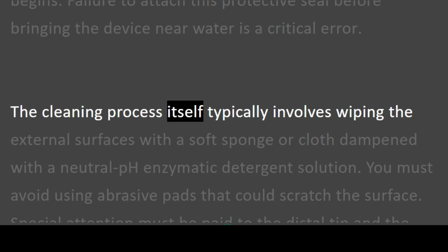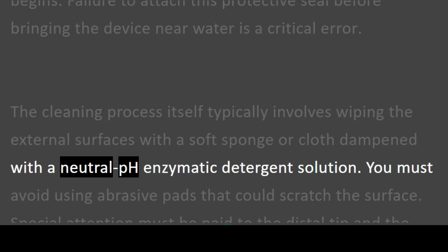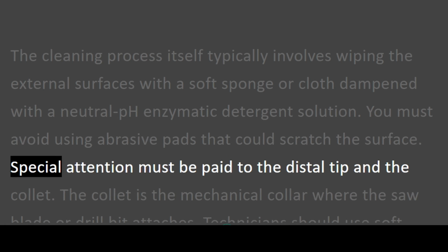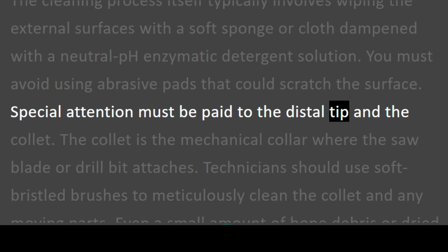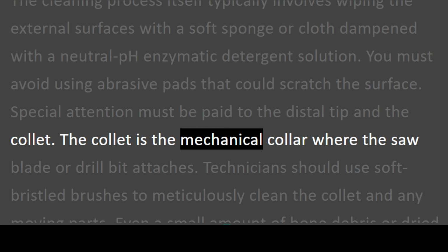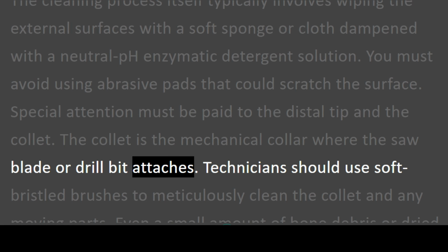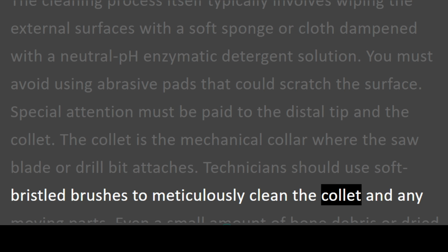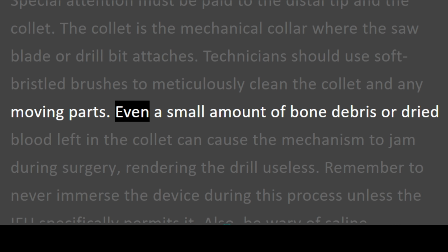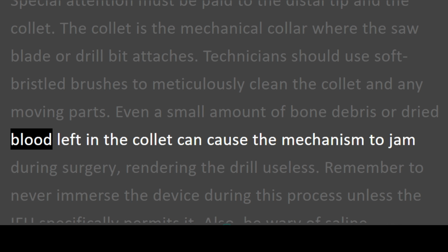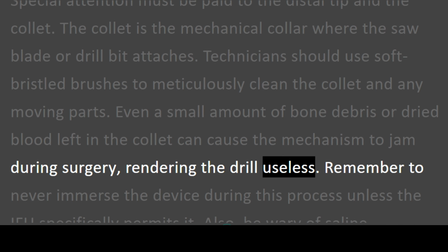The cleaning process itself typically involves wiping the external surfaces with a soft sponge or cloth dampened with a neutral pH enzymatic detergent solution. You must avoid using abrasive pads that could scratch the surface. Special attention must be paid to the distal tip and the collet. The collet is the mechanical collar where the saw blade or drill bit attaches. Technicians should use soft bristled brushes to meticulously clean the collet and any moving parts. Even a small amount of bone debris or dried blood left in the collet can cause the mechanism to jam during surgery, rendering the drill useless.